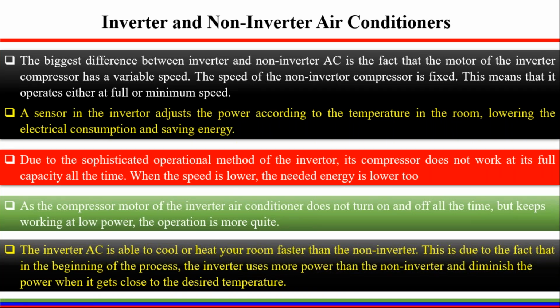There is a new technology, which is the inverter and non-inverter DC air conditioners. They are very efficient. They can reduce your bills, and I will explain a little bit about how the inverter and the non-inverter air conditioners differ. The biggest difference between the inverter and the non-inverter air conditioning is that the motor of the inverter compressor has a variable speed, and the speed of the non-inverter compressor is fixed. This means that it operates either at full speed or minimum speed. With non-inverters, you have only two options: either it runs at the minimum speed or it runs at the maximum speed.